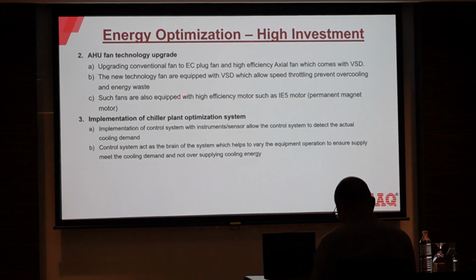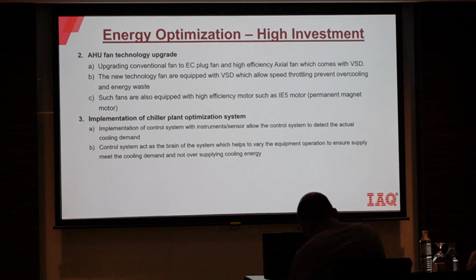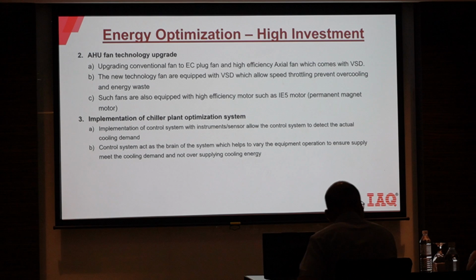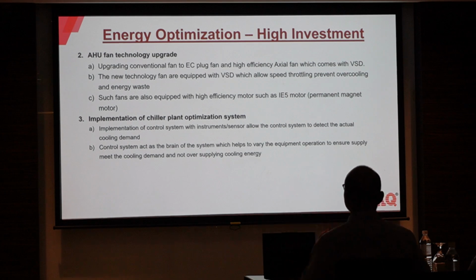Next is the air side. A few simple technology upgrades here include upgrading the conventional fan to EC plug fan and high efficiency axial fan that comes with VSD. The main thing is the VSD that allows throttling. Fan efficiency may only improve by a few percent, but throttling the speed will help you save a lot. There are also fans that use EC motor, permanent magnet motors.